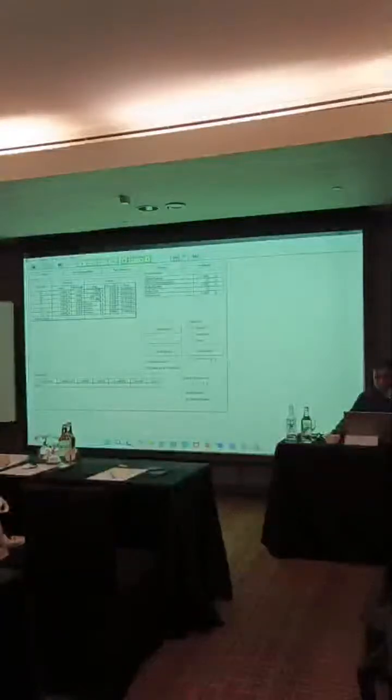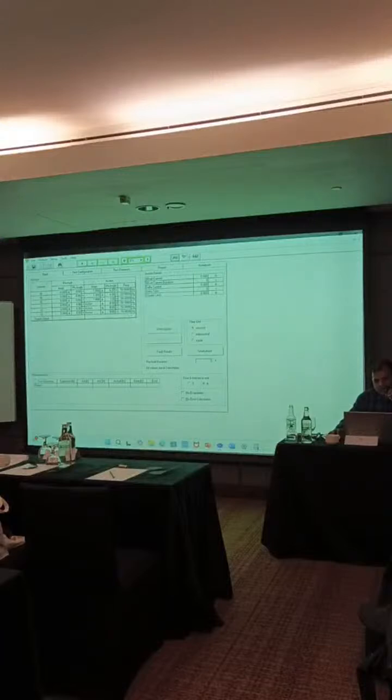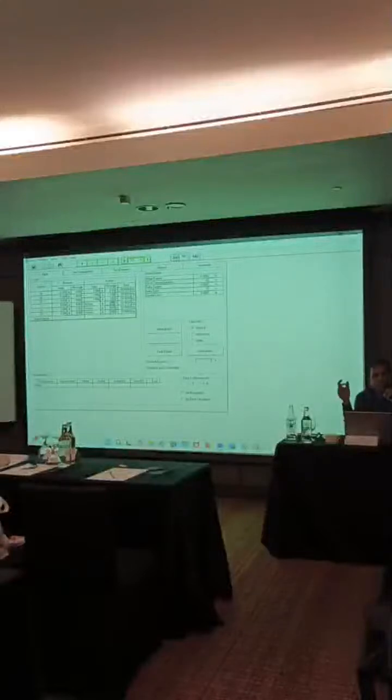So 1 will be easy in calculation, so we will put 1, and here balance, and if we are injecting in the same winding, then we will keep it in the same phase. If we are injecting through other winding, then we will select the 180-degree angle.